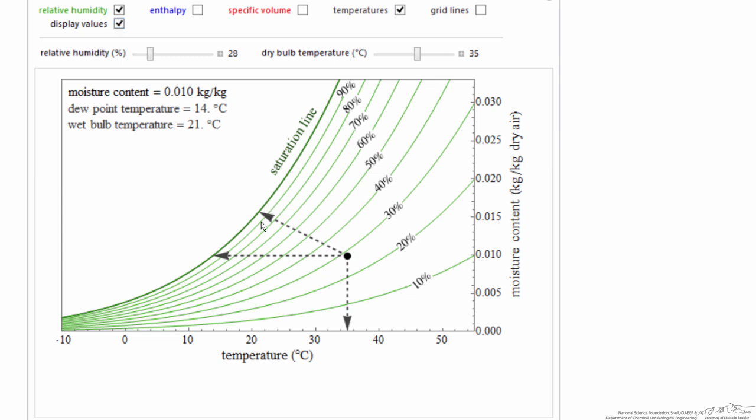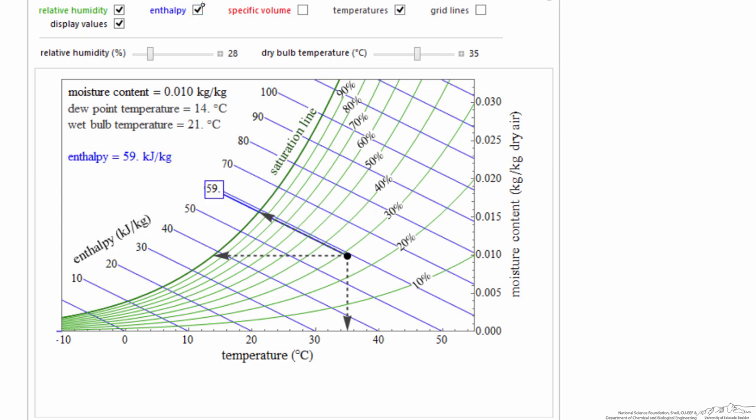So the wet bulb temperature is 21 degrees, that's something I can measure. Dew point is 14 degrees, and the wet bulb temperature corresponds fairly closely, not exactly, but that's what we're going to approximate as along a constant enthalpy line.